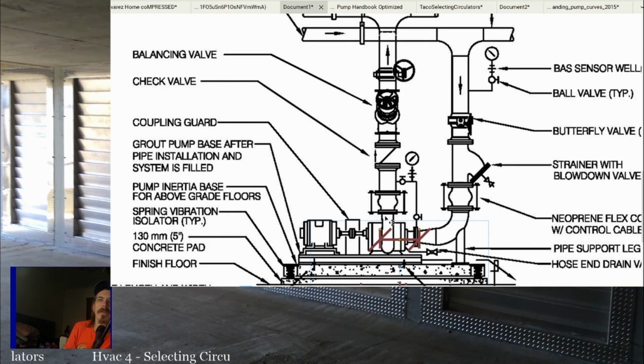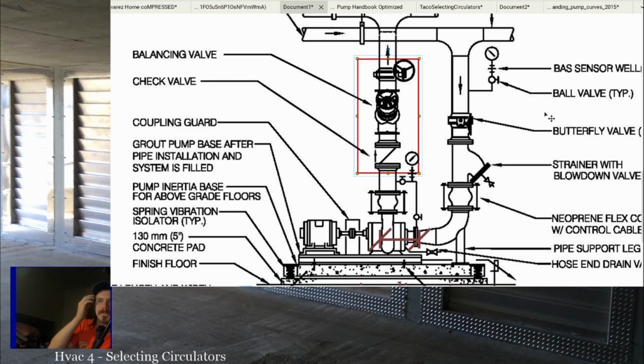Then you will have a check valve and a balancing valve and another shutoff valve. Sometimes, instead of having these 3 valves, you'll have what's called a triple duty valve. A triple duty valve is 3 valves in one. It is a check valve, a balancing valve, and a shutoff valve. It's really only 2 valves. It's a balancing valve that can be used as a shutoff valve and a check valve, but it can serve all 3 purposes. Notice our check valve is after our pump. Our balancing valve is after our pump. And then we have another shutoff valve, primarily for service.